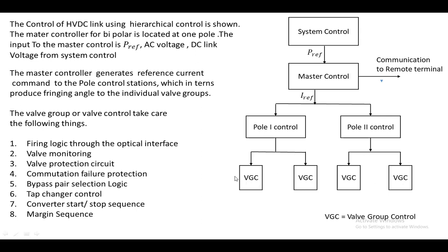The VGC — valve group control — not only provides firing commands to the valve, it also takes into consideration the firing logic through optical sensors. The firing angle generated is transmitted to the device through optical fiber. Second is the valve monitoring system, which determines whether the valve is working properly or if it is damaged — that information is also taken into consideration by the VGC. Third is the valve protection system: to protect the valve, some hardware circuit is used alongside the valve, and that is also considered by the VGC.